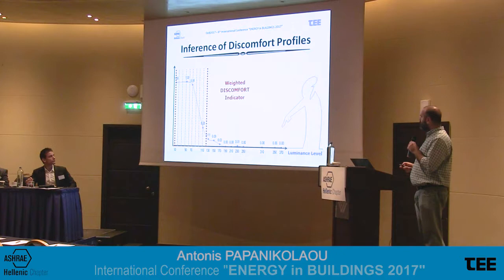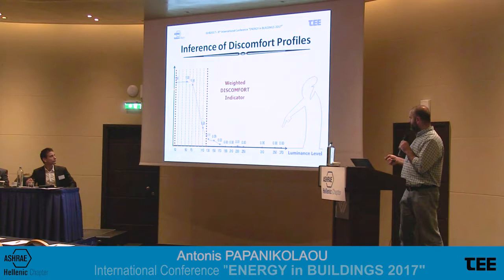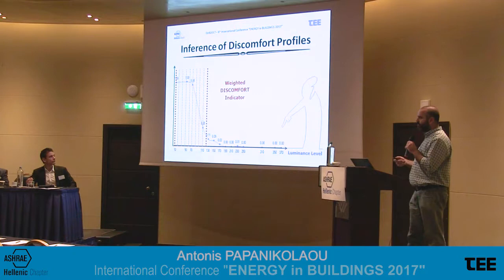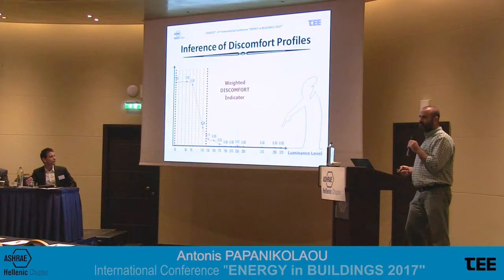By gathering all these different signals plus a few more, we can make what we call a discomfort profile. This is a curve where the horizontal axis is the luminance level — this is in lux but it can represent anything else. This blue curve is actually a weighted indicator that signifies the visual discomfort of individuals — what conditions they are happy with. We take an arbitrary threshold and say that a value of 0.11 means that the comfort level at 120 lux is 89%, and anything below that is unacceptable.